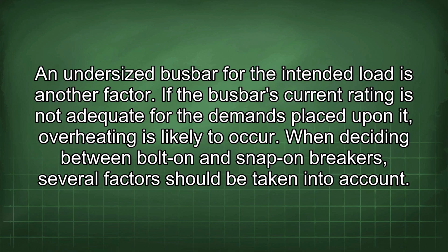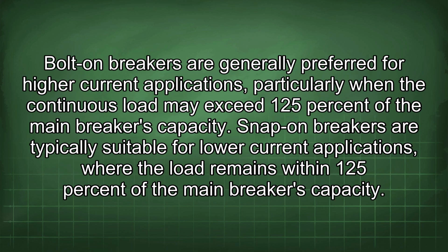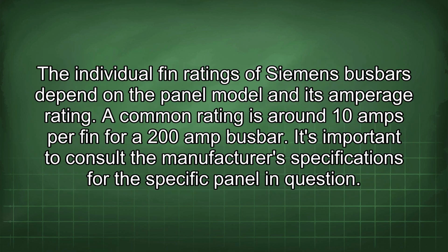When deciding between bolt-on and snap-on breakers, several factors should be taken into account. Bolt-on breakers are generally preferred for higher current applications, particularly when the continuous load may exceed 125% of the main breaker's capacity. Snap-on breakers are typically suitable for lower current applications, where the load remains within 125% of the main breaker's capacity. The individual fin ratings of Siemens busbars depend on the panel model and its amperage rating. A common rating is around 10 amps per fin for a 200 amp busbar. It's important to consult the manufacturer's specifications for the specific panel in question.